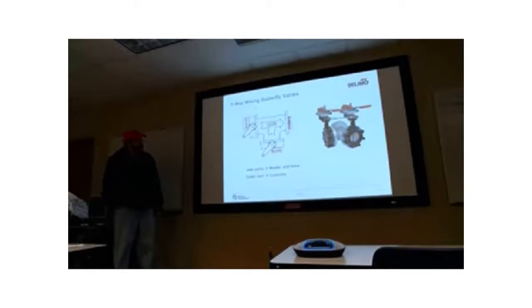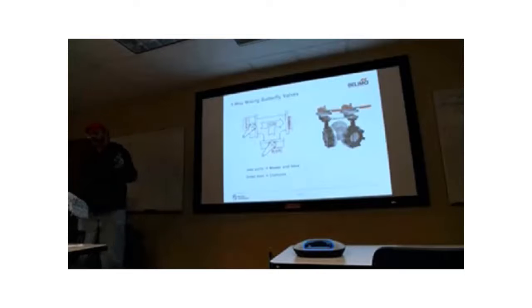You guys deal with butterfly valves much? Or no? Some? All right, now on a butterfly valve, this is just sort of general nomenclature. With a three-way mixing valve, first of all, just some nomenclature. If you're looking at a three-way butterfly valve, first thing you basically know about this is that there's no such thing really as a three-way butterfly valve. But what there really is, what? Two ways bolted onto a T. That's how you make a three-way butterfly, right?